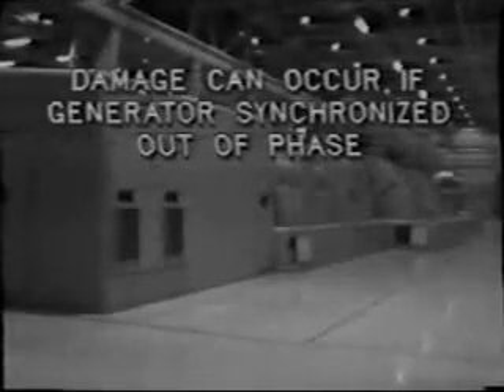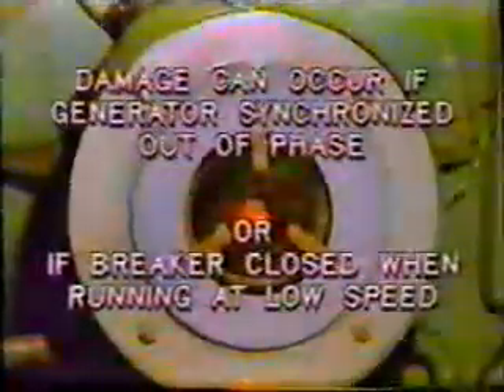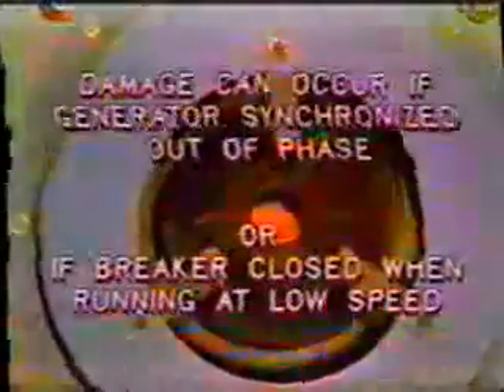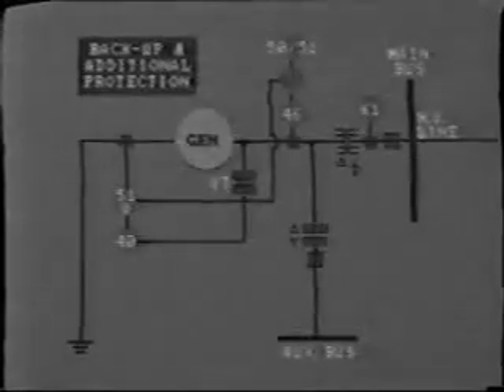Serious damage can occur to the generator if it is synchronized out of phase, or even worse, if the breaker is inadvertently closed when the unit is on turning gear or running at low speed. In any of these situations, an extremely high current will flow into the generator windings. Protection against this potential hazard is provided by connecting directional time overcurrent relays, one in each phase. For power flow into the generator, this relay, device number 67, will operate and trip. Another type of relay which is often installed is a synchronizing relay. This will not allow the breaker to close unless the phase angle is within a determined range, usually 10 degrees either side of synchronism.